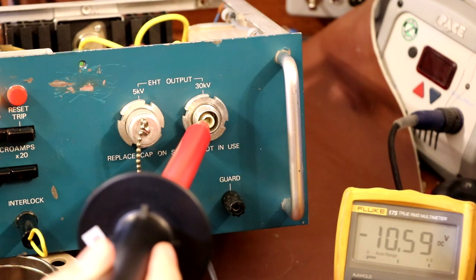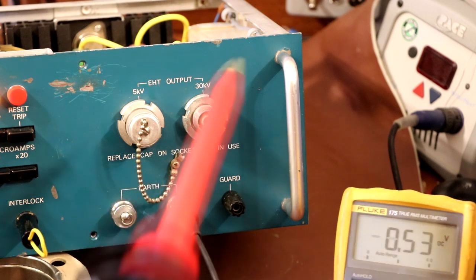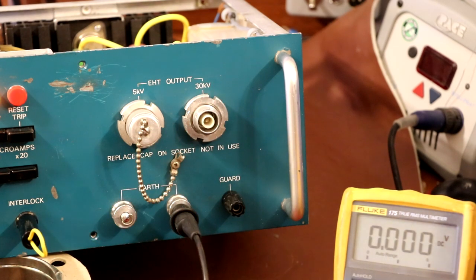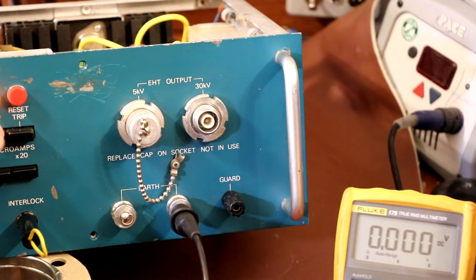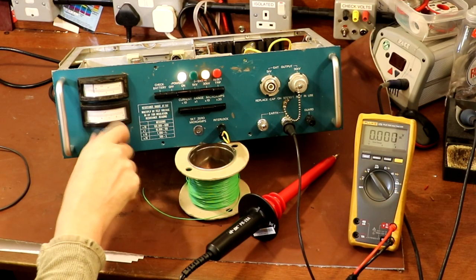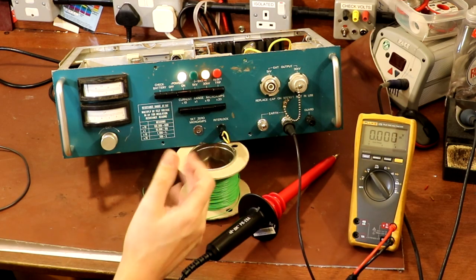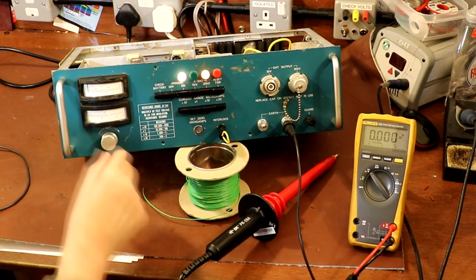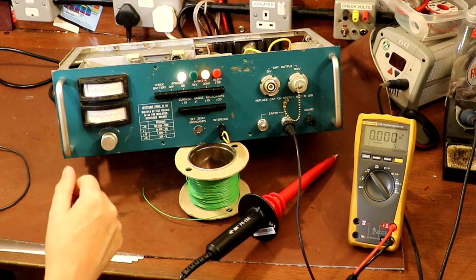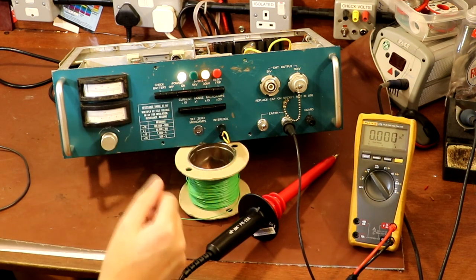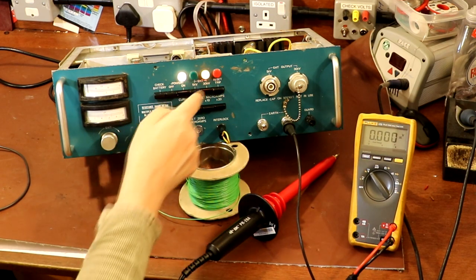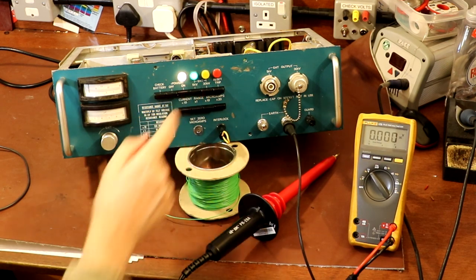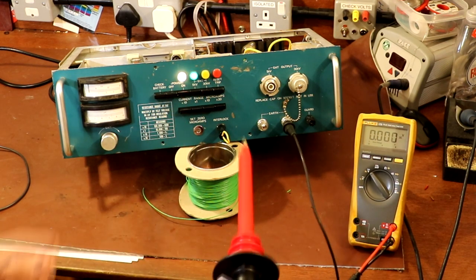Okay, so that's 10,000 volts. So I would say that we've actually got a winner here. So I'm going to turn that off. Okay, so that's fine. So when it's actually got a mating connector in it, that connector doesn't flash over. So we need the right connector to use there. We need something that will withstand 30 kilovolts, because obviously the test setup I'm using at the moment just can't do that. Right, let's try the 5 kV range again, because that was all a little bit more sensible.